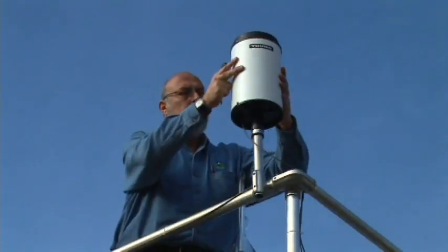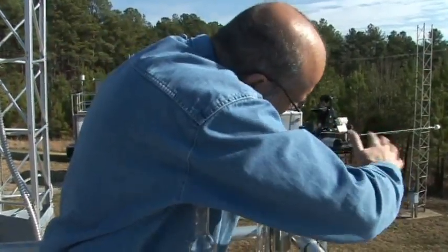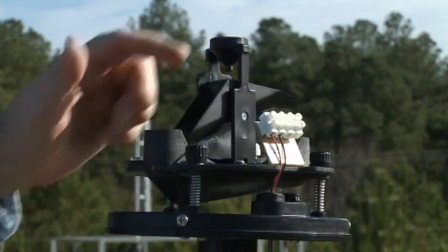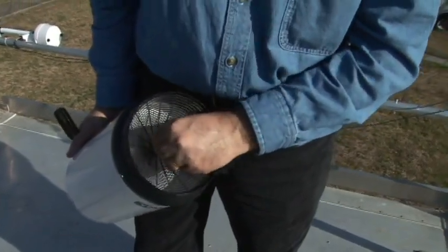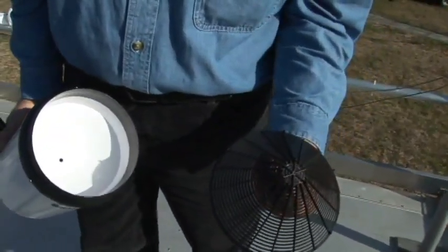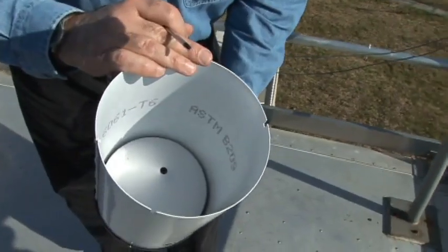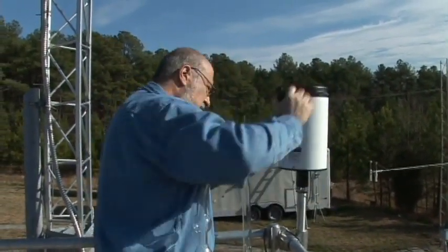Once the rain enters the funnel, all rainfall will run down to the opening and enter the measurement portion of the gauge. At this time, the technician will remove the funnel and inspect the tipping bucket. There are two important issues to note when inspecting the tipping mechanism. First, is there any debris that could cause the mechanism to not work properly or make the tipping mechanism stick? The second item to note, are there any insects or spiders that inhabit the inside of the gauge? If so, these must be removed and the tipping mechanism cleaned. After the technician has cleaned the inside of the gauge, be sure to reinstall the funnel and housing.